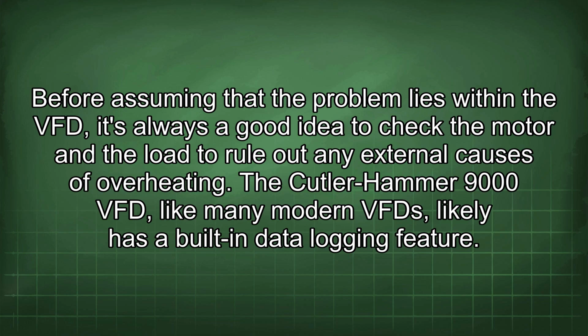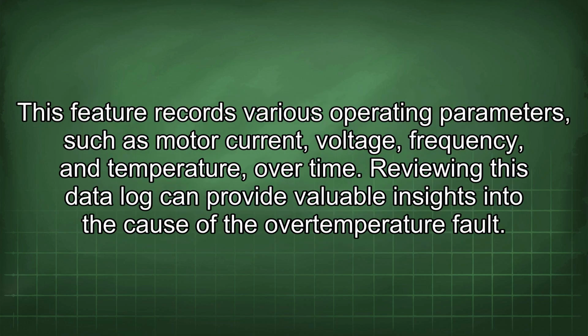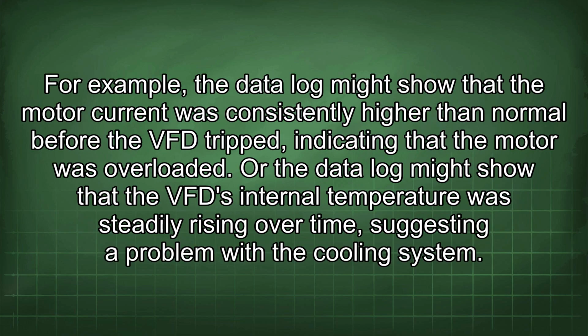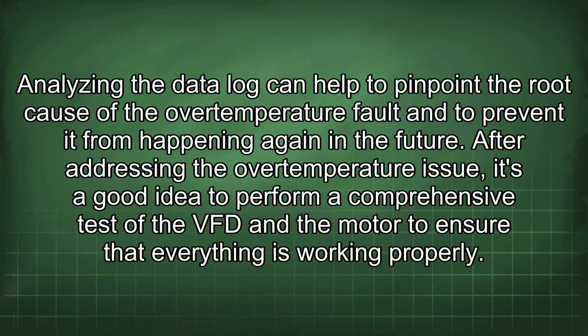The Cutler-Hammer 9000 VFD, like many modern VFD, likely has a built-in data logging feature. This feature records various operating parameters, such as motor current, voltage, frequency, and temperature over time. Reviewing this data log can provide valuable insights into the cause of the overtemperature fault. For example, the data log might show that the motor current was consistently higher than normal before the VFD tripped, indicating that the motor was overloaded. Or the data log might show that the VFD internal temperature was steadily rising over time, suggesting a problem with the cooling system. Analyzing the data log can help to pinpoint the root cause of the overtemperature fault and to prevent it from happening again in the future.